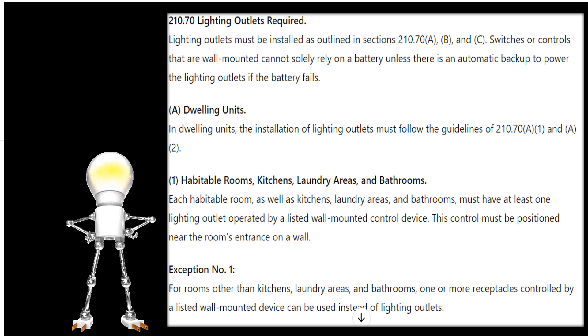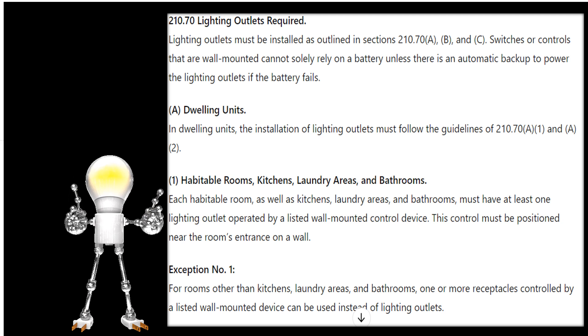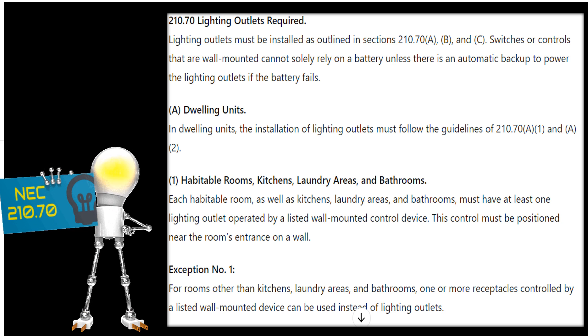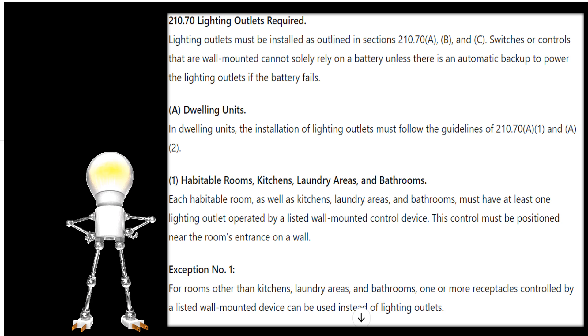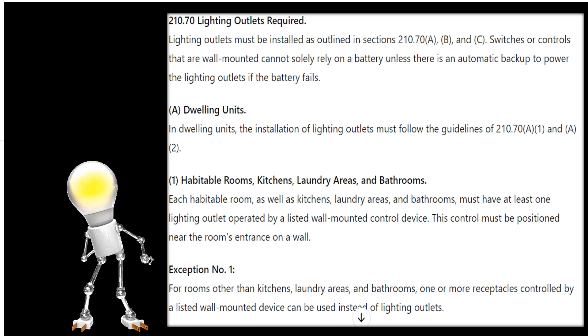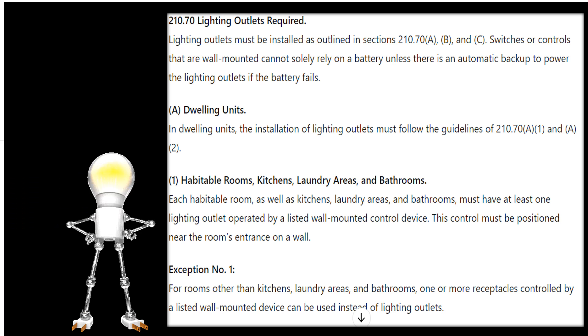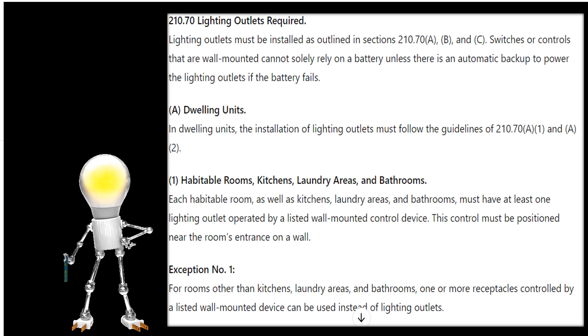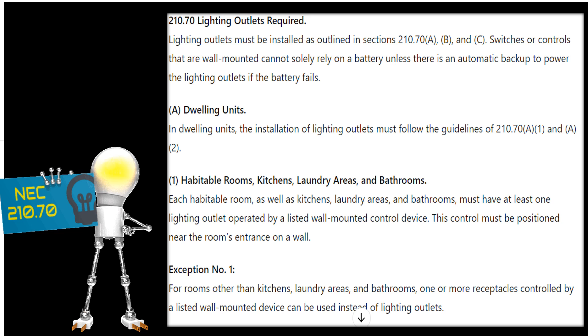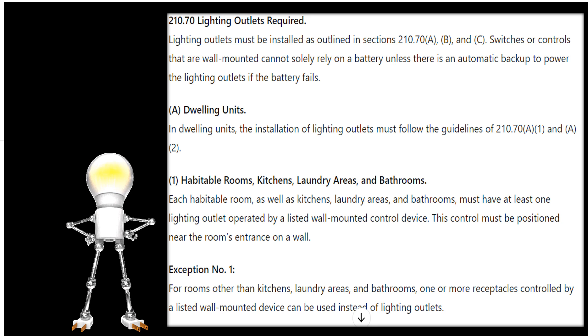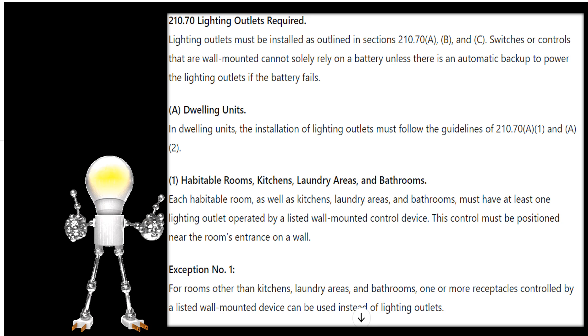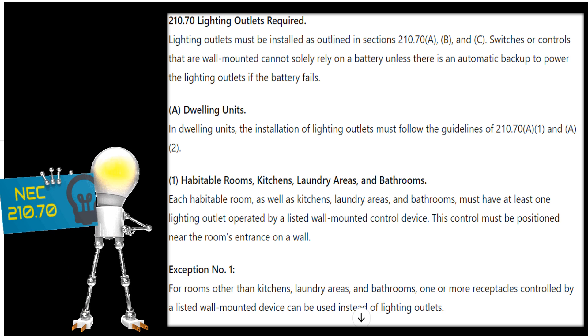A lot of this was new code language in the 2020 NEC. The NEC now recognizes that a listed wall-mounted control device could mean anything — it could be a remote control device, or a general snap switch like we're used to seeing. It doesn't necessarily have to be a switch. Similarly, the control must be positioned near the room's entrance on the wall — that language was brought in with the 2020 and held true in the 2023.